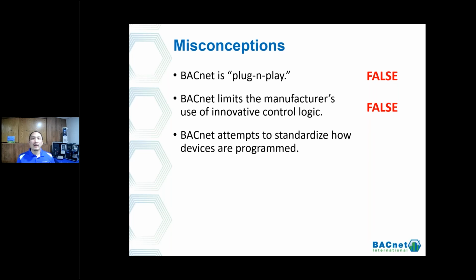Another misconception: BACnet attempts to standardize how devices are programmed. Again, it doesn't tell us your device has to program this way or that way. A lot of vendors have already defined the way they want it done. They've done it for years and years, and they're not going to make that change. It's a lot of things to do when you make someone change that way. But they know that if they can create that interface to get the information of their device out in the way they specified, they've made a step forward to make it easier for the user.